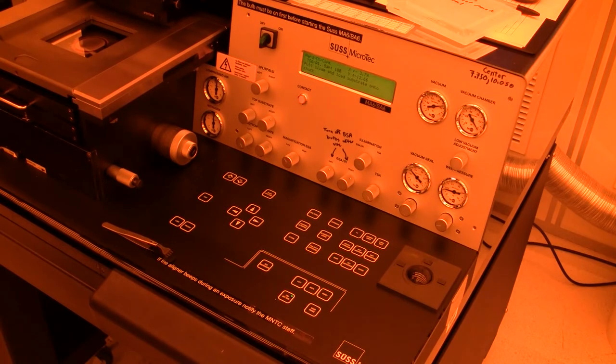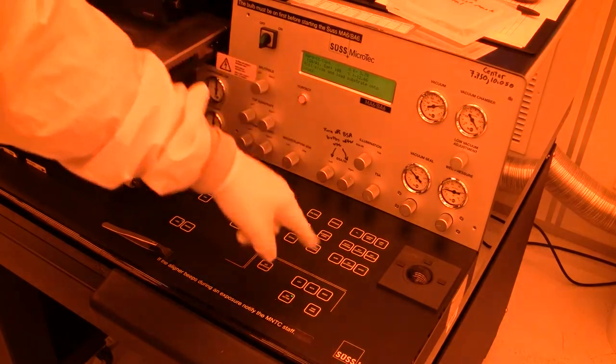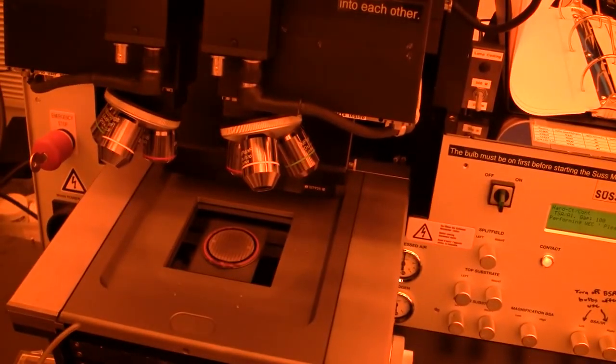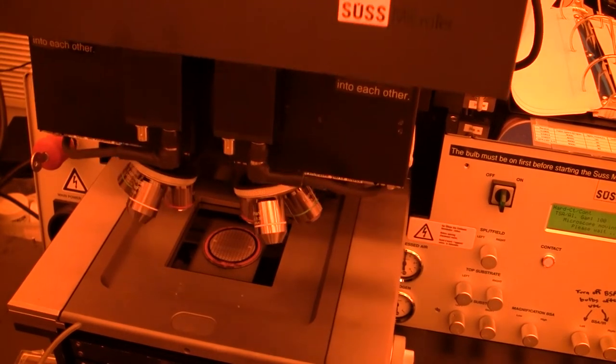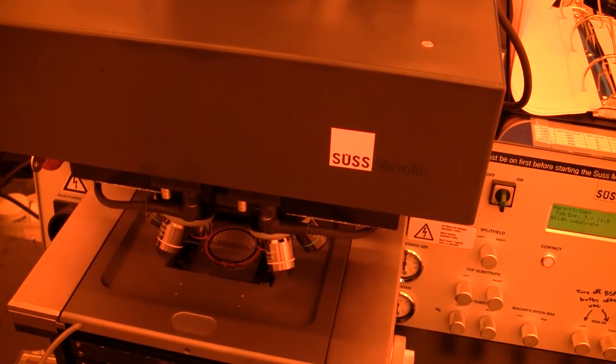It says pull slide and load substrate under chuck, press enter. The wafer rises up to contact the mask. I'm performing a WEC - this is wedge error compensation. And then the optics come down to do alignment.